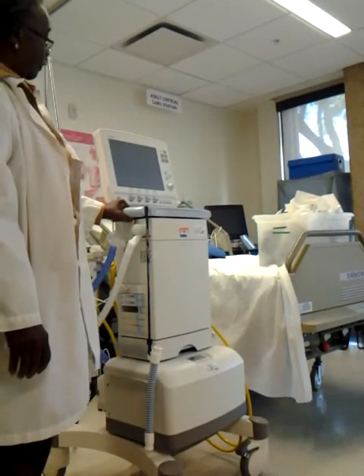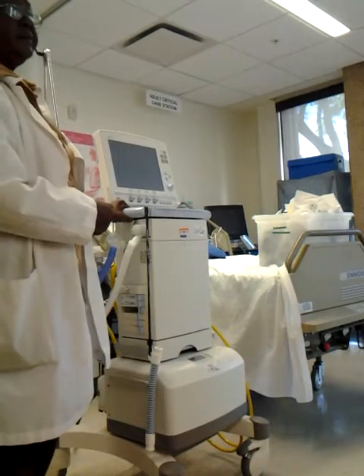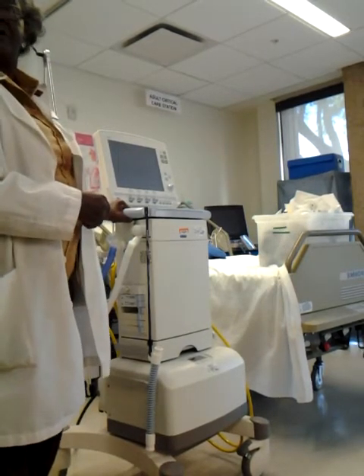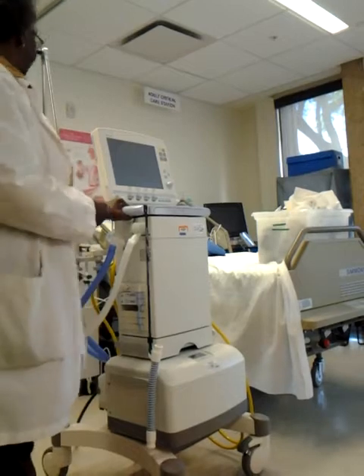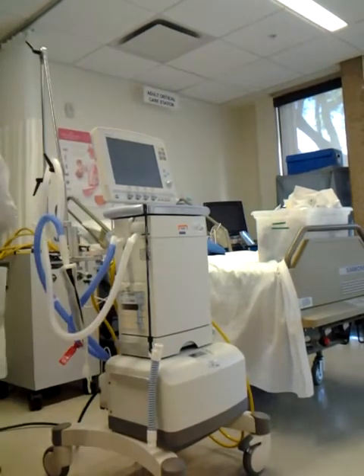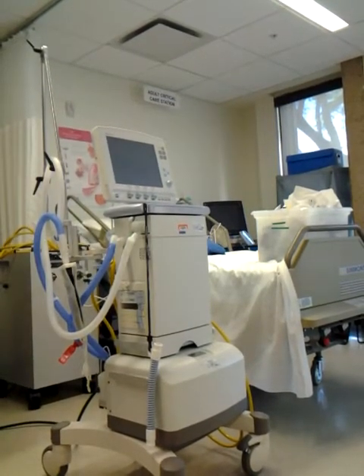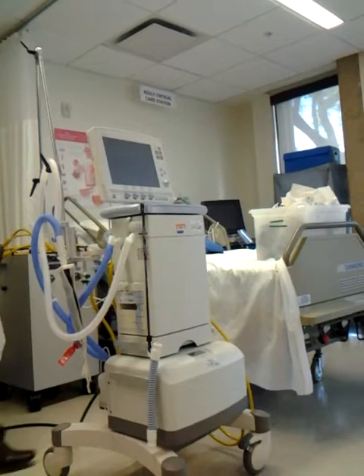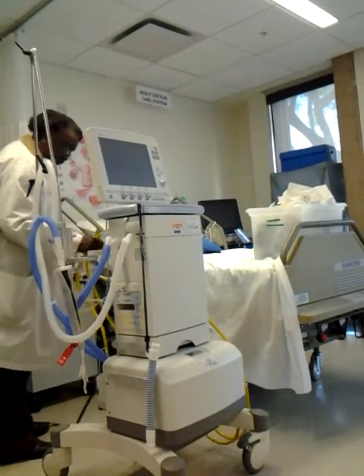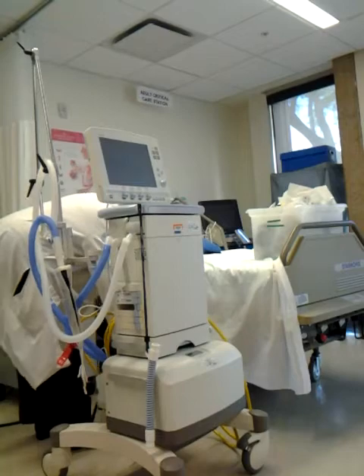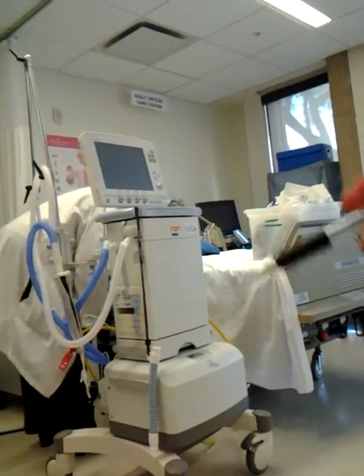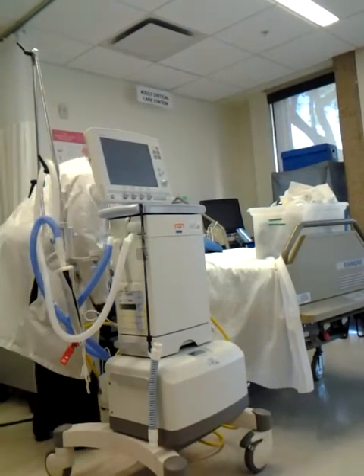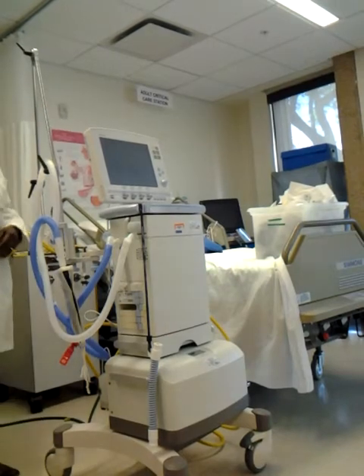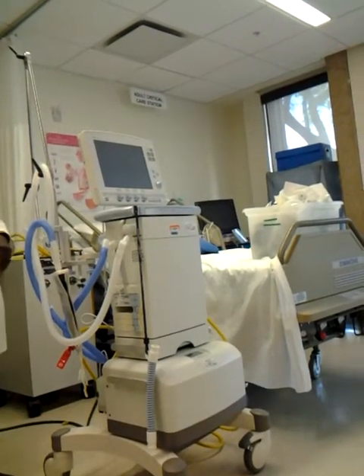Okay. Like the 840, it has to go through its little test every time you hook it up. And I have a little oxygen hooked up here so we can do that. I'm also going to hook up the air hose so we don't burn out the compressor. Put the two filters on there so we can see what it looks like. Somebody who's taking the air hose off here, we do that every year. Okay, so we'll use the short filters? Is that why we're not using them on the compressor?